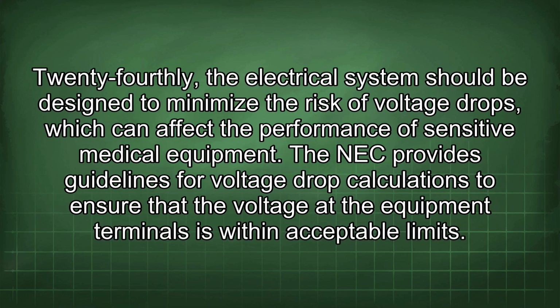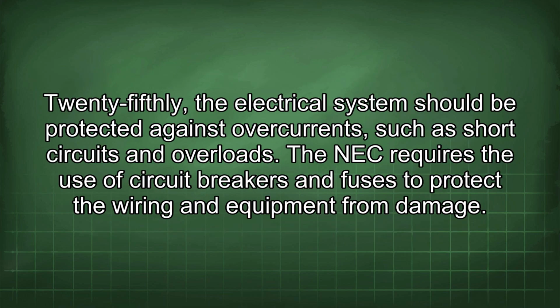24thly, the electrical system should be designed to minimize the risk of voltage drops, which can affect the performance of sensitive medical equipment. The NEC provides guidelines for voltage drop calculations to ensure that the voltage at the equipment terminals is within acceptable limits. 25thly, the electrical system should be protected against overcurrents such as short circuits and overloads.